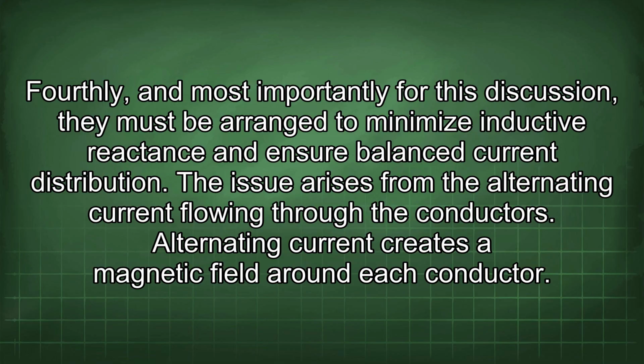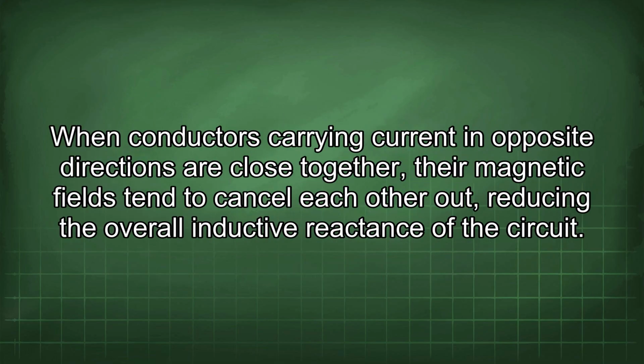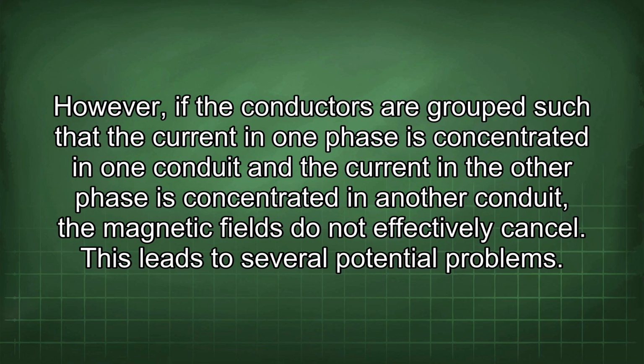The issue arises from the alternating current flowing through the conductors. Alternating current creates a magnetic field around each conductor. When conductors carrying current in opposite directions are close together, their magnetic fields tend to cancel each other out, reducing the overall inductive reactance of the circuit. However, if the conductors are grouped such that the current in one phase is concentrated in one conduit and the current in another phase is concentrated in another conduit, the magnetic fields do not effectively cancel.